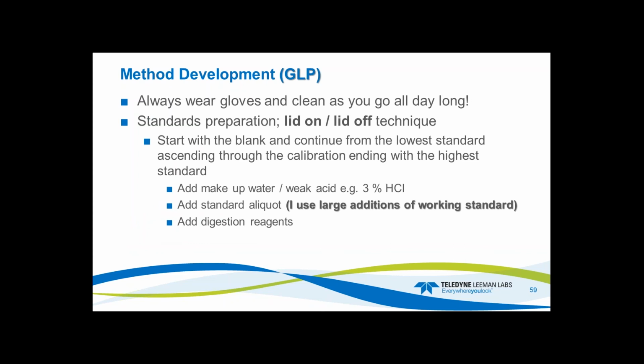So I use the standards lid on, lid off technique. What I do is I start with the blank, and then I add my makeup water, weak acid, 3% HCl, whatever I'm using. Add a standard aliquot. I like large additions. So if you're using a 50 ml test tube with a cap or volumetric flask, whatever, I do not like using 10 microliters, 50 microliters, 100 microliters into large volumes. That just introduces too much error. So I like large volume additions into my calibration standards.